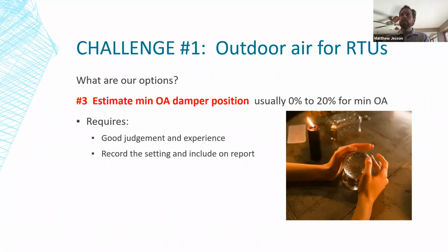And it's important, if you do this, to record what that setting is and how you determined it, and include that on the TAB report. And I should point out that sometimes that outdoor air damper position is set through a controller or through the DDC system, where you actually dial in the exact percentage and it goes to that position. But on some rooftop units with simpler controls, it might just be a little potentiometer on the control board of the rooftop unit, in which case it might not have a percentage that you can really mark down. So what we'll do sometimes is go to the damper itself once we've got it set where we want, and just measure the gap in between the blades and say the minimum outdoor air damper position was set to 3/4 inch of open, which provides a good way to check it in the future.